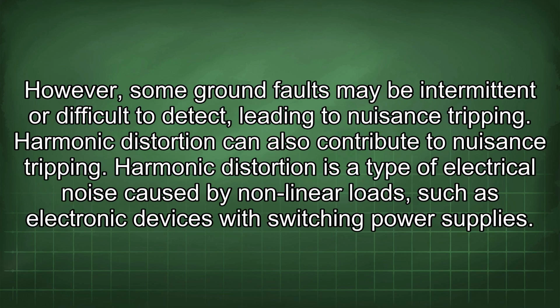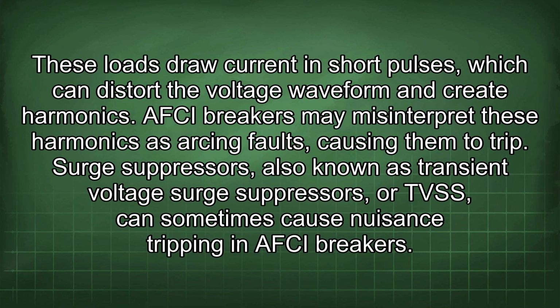However, some ground faults may be intermittent or difficult to detect, leading to nuisance tripping. Harmonic distortion can also contribute to nuisance tripping. Harmonic distortion is a type of electrical noise caused by nonlinear loads such as electronic devices with switching power supplies. These loads draw current in short pulses, which can distort the voltage waveform and create harmonics. AFCI breakers may misinterpret these harmonics as arcing faults, causing them to trip.